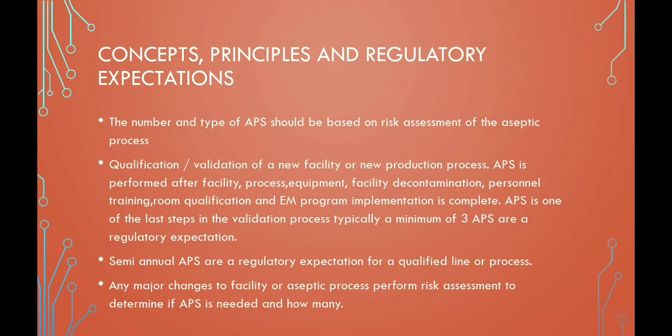Semi-annual — that is, twice a year — aseptic process simulations are the regulatory expectation for a qualified line or process. For any major changes to a facility or aseptic process, a risk assessment should be performed to determine if aseptic process simulation is needed and how many.